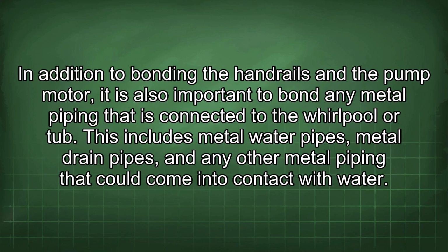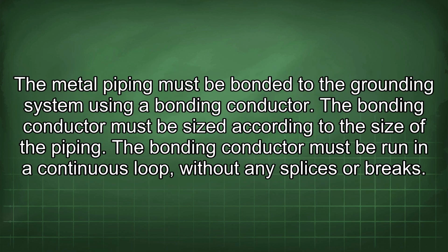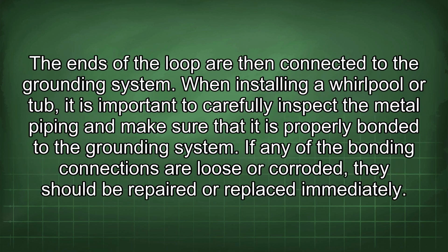In addition to bonding the handrails and the pump motor, it is also important to bond any metal piping that is connected to the whirlpool or tub. This includes metal water pipes, metal drain pipes, and any other metal piping that could come into contact with water. The metal piping must be bonded to the grounding system using a bonding conductor. The bonding conductor must be sized according to the size of the piping. The bonding conductor must be run in a continuous loop, without any splices or breaks. The ends of the loop are then connected to the grounding system.